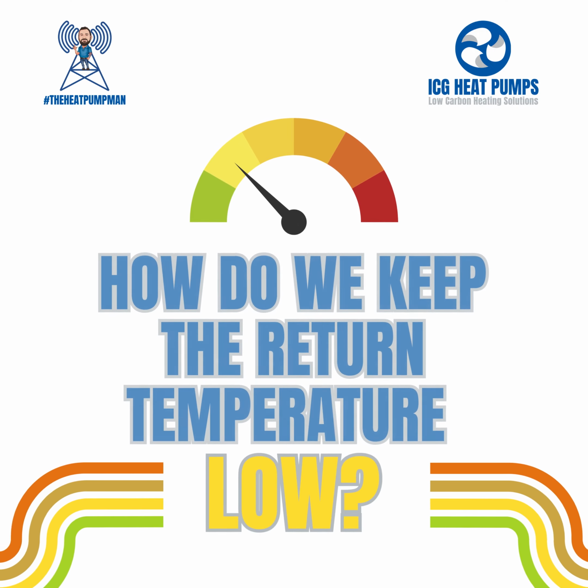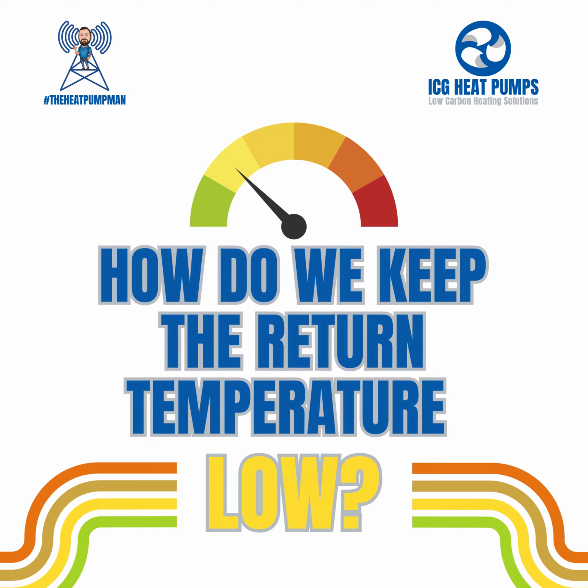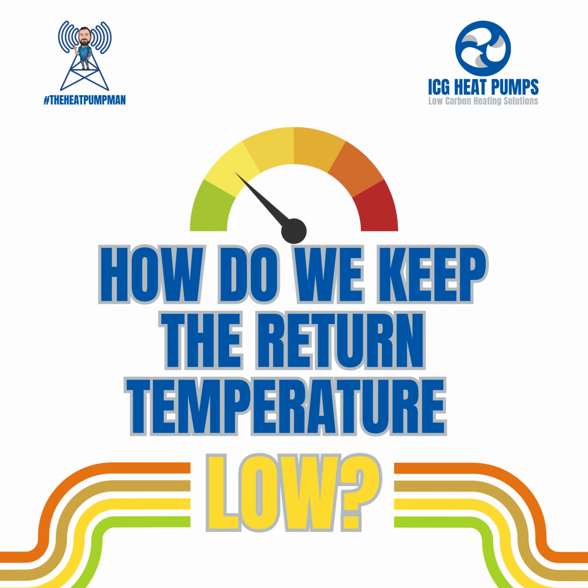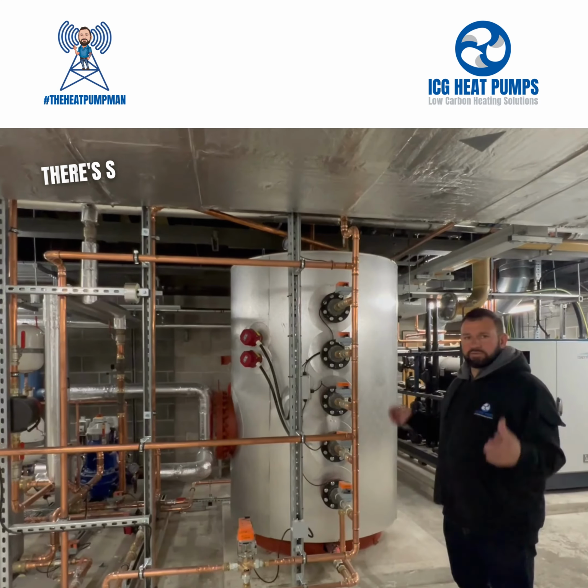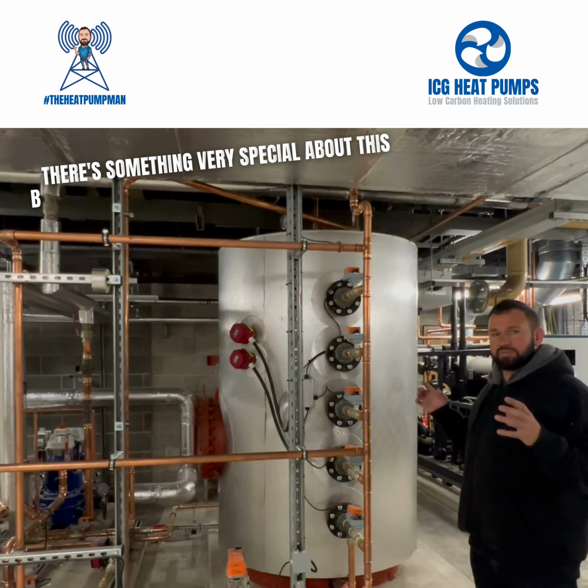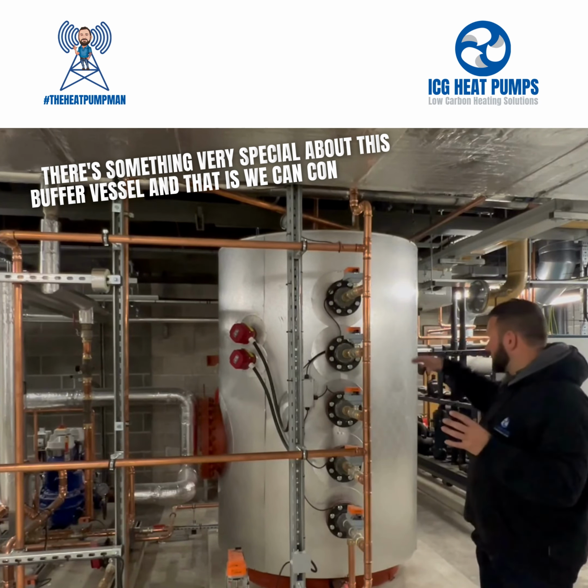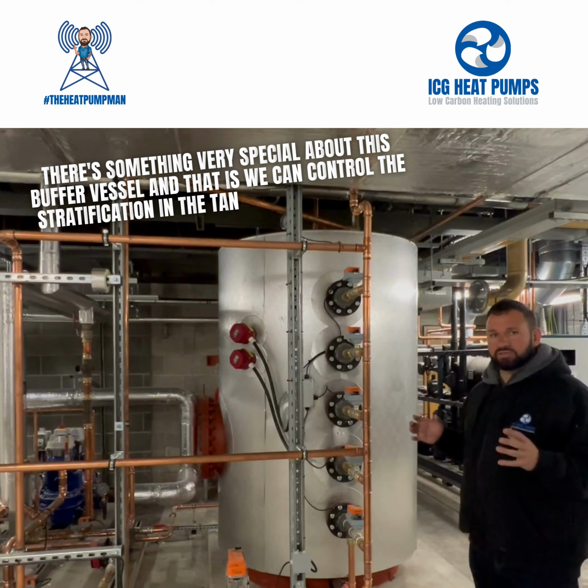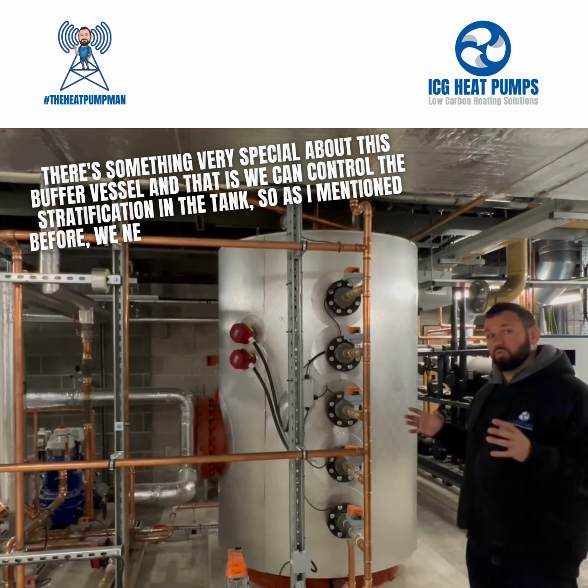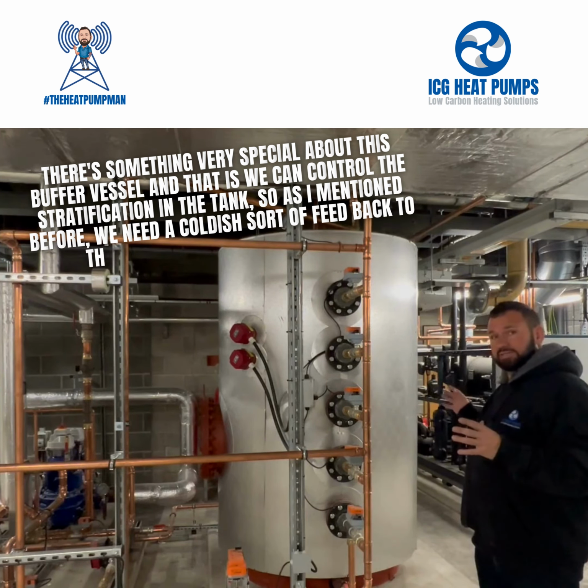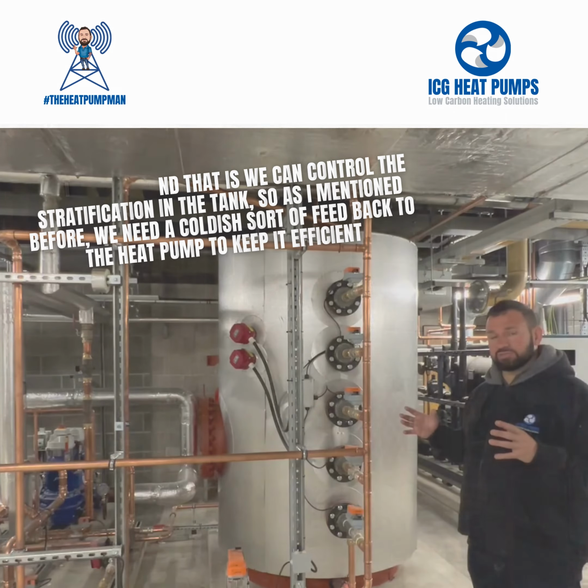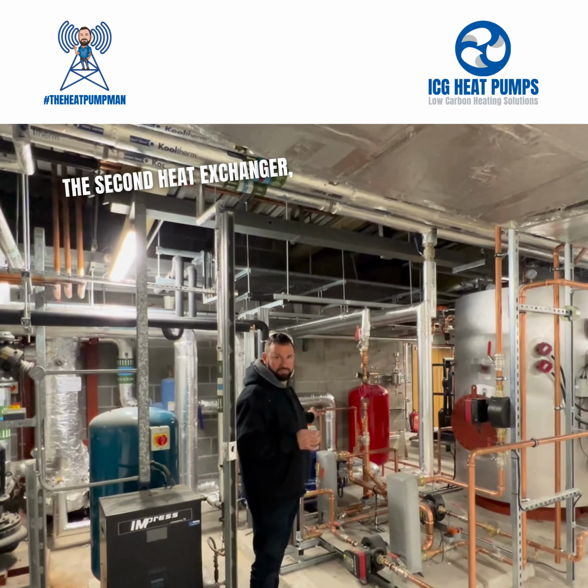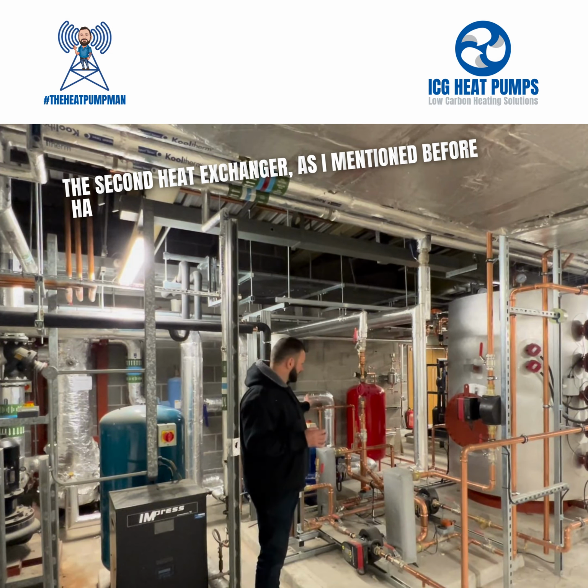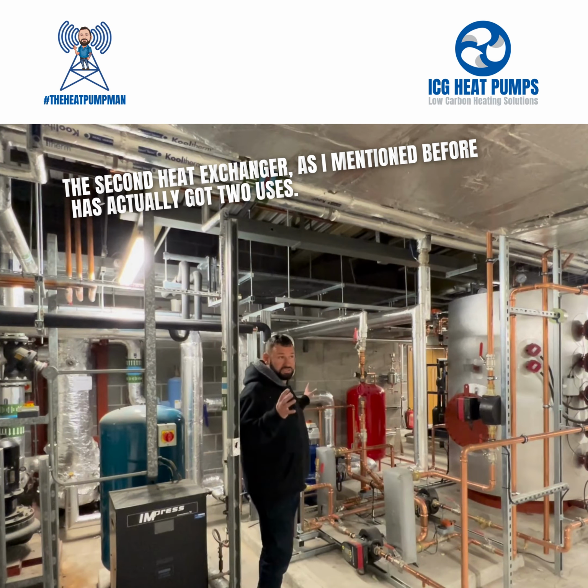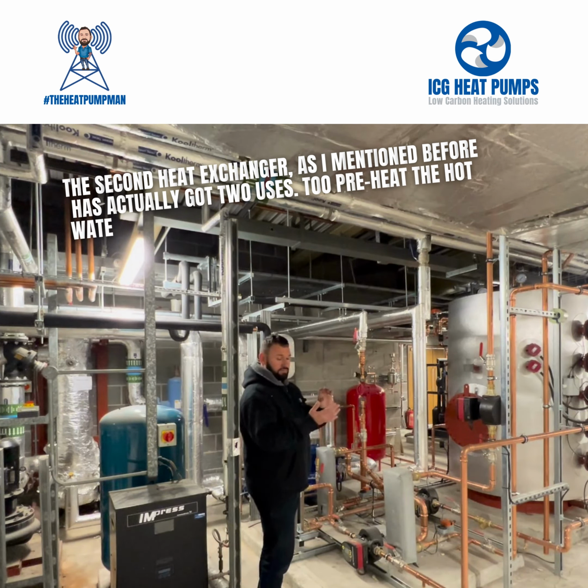The question everyone asks is, how do we keep the return temperature low? Something very special about this buffer vessel, and that is that we control the stratification in the tank. So as I mentioned before, we need a coldish sort of feed back to the heat pump to keep it efficient.